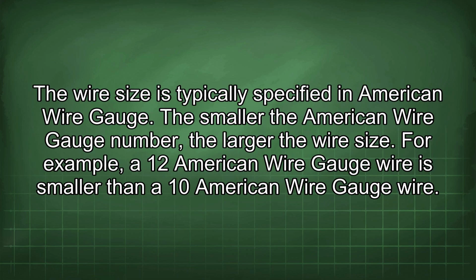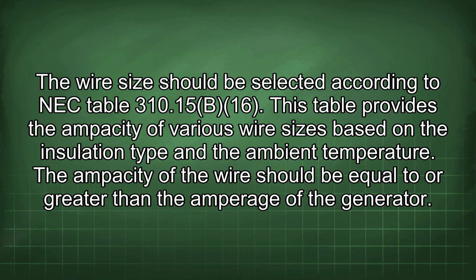The wire size is typically specified in American wire gauge. The smaller the American wire gauge number, the larger the wire size. For example, a 12 American wire gauge wire is smaller than a 10 American wire gauge wire. The wire size should be selected according to NEC Table 310.15(B)(16). This table provides the ampacity of various wire sizes based on the insulation type and the ambient temperature. The ampacity of the wire should be equal to or greater than the amperage of the generator.